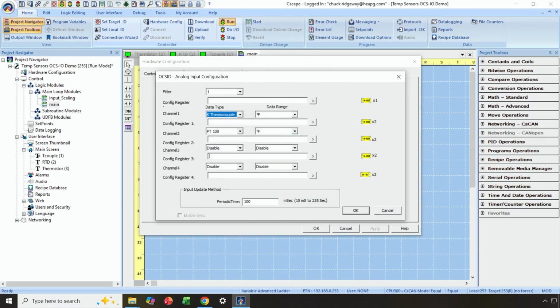Okay, so this is a 4-channel module. It has the ability to do filtering. If you'd like to filter the values for a little slower response and maybe a little more stability, you can do that. I've got that pretty much set to a minimal value. And then for each channel, you've got the capability of selecting from a pretty wide list of sensor types. So 0 to 10 volt signals, 0 to 20 milliamp, 4 to 20 milliamp. It can even handle millivolt levels for things like certain strain gauge type applications or load cell type applications. And then you can see it supports a whole variety of thermocouple types, and of course, a couple different types of RTDs, Platinum 100 and Platinum 1000.